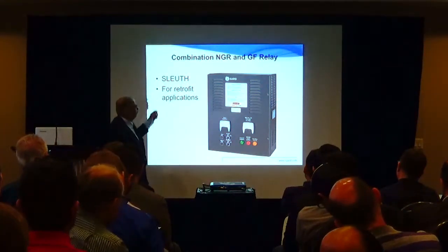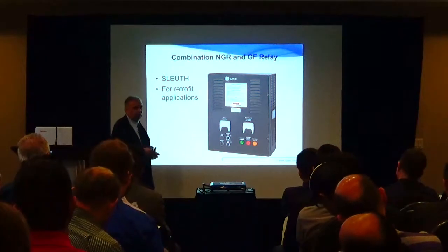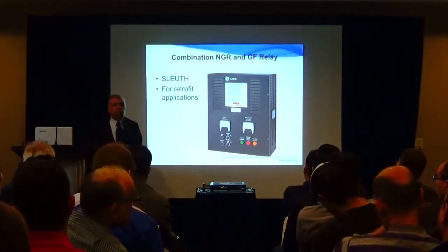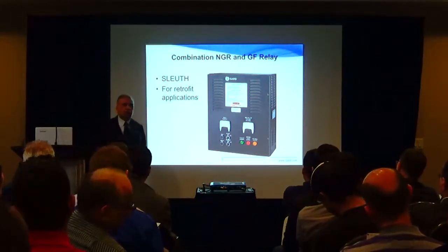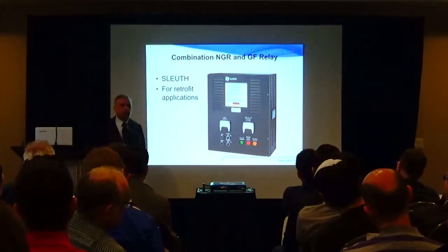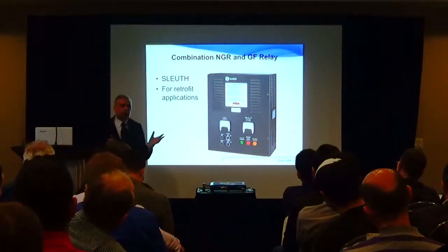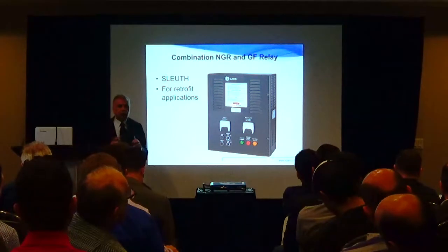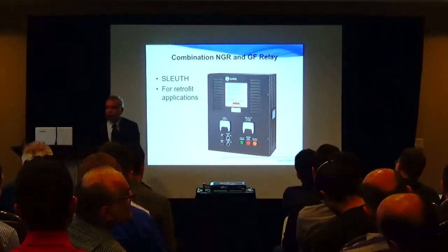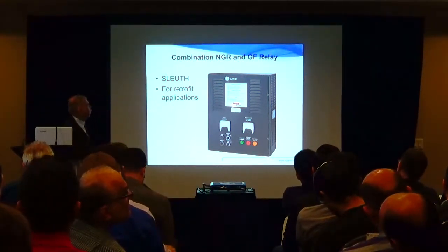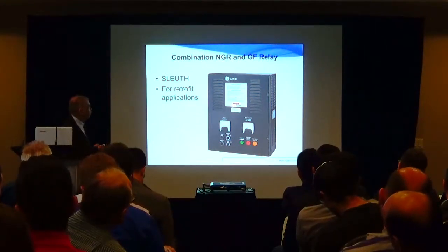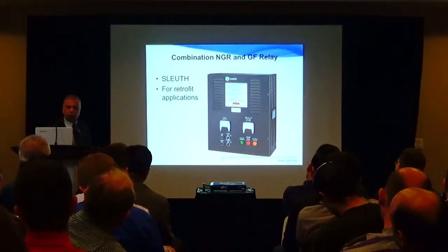So this is called a detective system, because it helps you find the fault. The resistors are not simple resistors anymore. They are resistors with control associated with them. You bring 120 volt control to it, bring the neutral in, and put it on the wall. So it's independent of the switchgear and independent of the transformer. It's a separate unit that's conveniently mounted, easily applied wherever it's suitable, particularly for retrofit applications where you want to convert ungrounded to resistor grounded systems.